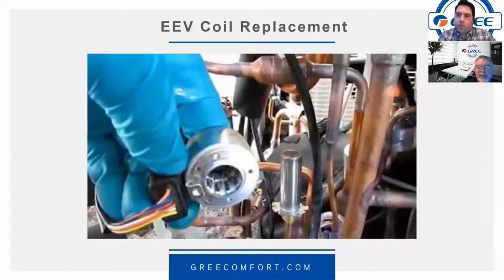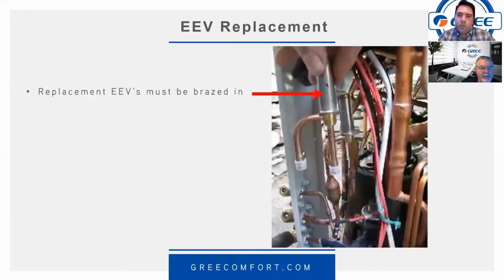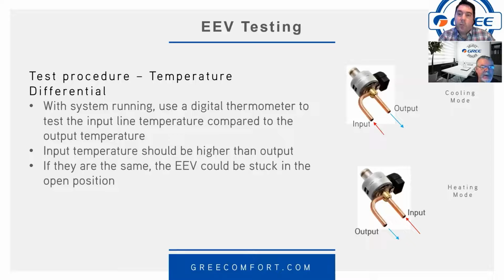And so you can replace the coils very easily. They pop right off there, and then the harness, you can unplug it from the board and fish a new one in there, if that's necessary. If you have to replace the entire valve, again, you've got to braze it in there. And so this is what the part looks like that you get. And again, use some thermal paste or a cloth or something to protect the valve. And flow nitrogen. And flow nitrogen, yes.